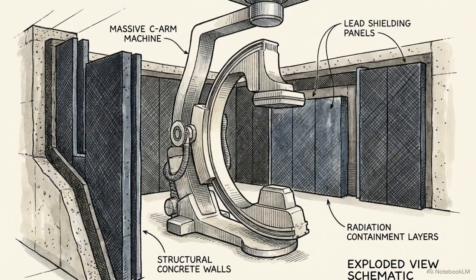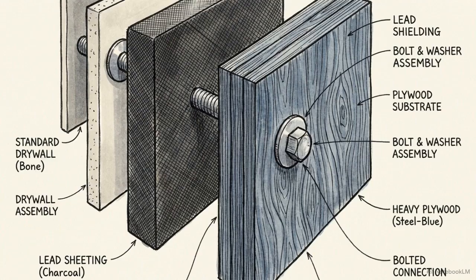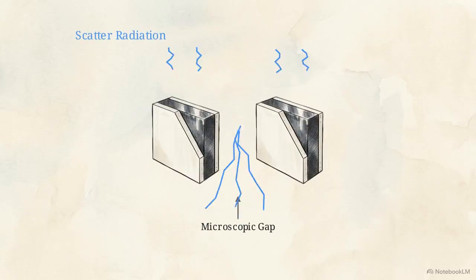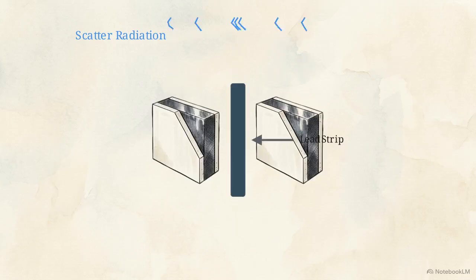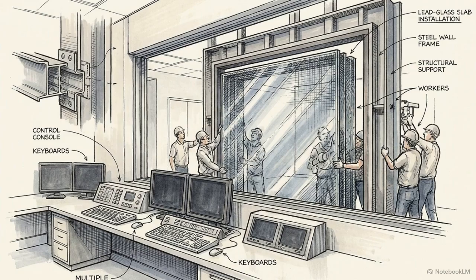The immediate priority is the containment of continuous, high-kilovolt scatter radiation produced during live fluoroscopy. The shielding architecture relies on lead-lined drywall and plywood. Because radiation can leak through microscopic gaps, every seam must be overlapped with thick lead strips, and the control room is protected by massive custom-fabricated lead glass windows exceeding 48 by 36 inches.